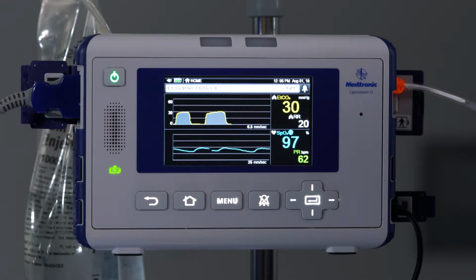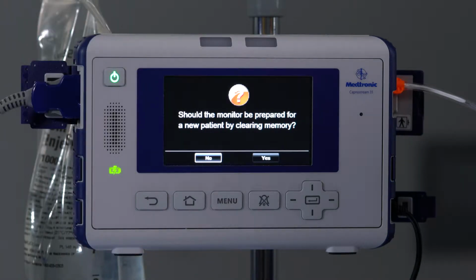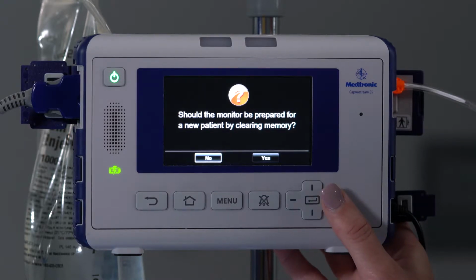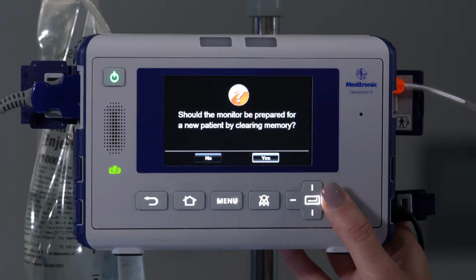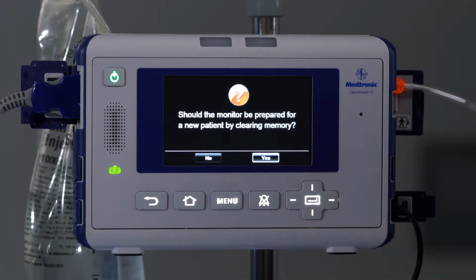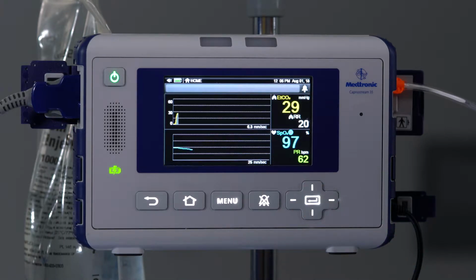If you're not in EMS mode, the monitor will always ask the question, should the monitor be prepared for a new patient by clearing memory? If it's the same patient, then you hit no. This will save the patient history. If it's a new patient, select yes, which will erase any memory so you can start over. Selecting yes will erase the memory and reset the patient alarm limits per the institutional default set by your facility. Selecting no keeps the last 48 hours of memory and any setting changes.